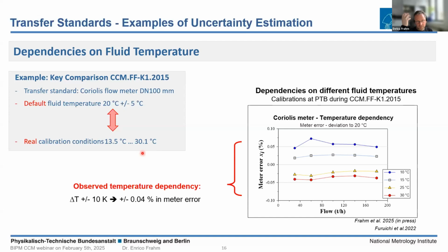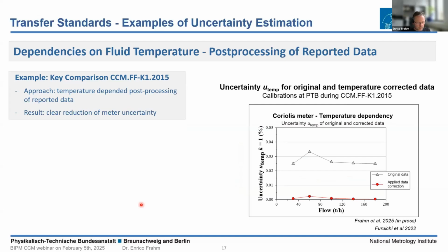So based on this motivation, we made characterization measurements using this Coriolis flow meter, and we found a very strong temperature dependency of the meter under test. So temperature changes of plus minus 10 Kelvin led to plus minus 0.04% in meter error. So this is, in the background of meter uncertainty and confirmed lab uncertainties, quite important to know. So this clear temperature dependency of meter error was used for a post-processing correction of the data, which resulted in a clear reduction of meter uncertainty.